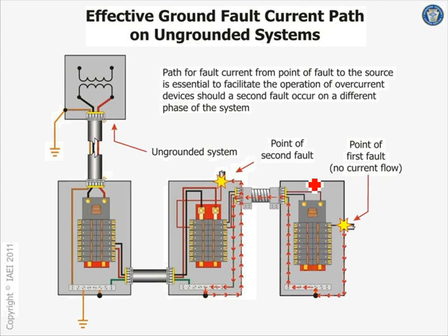You come over here. If you own and operate, you pull an equipment grounding conductor here. If you own and operate, then you come over here and create your own grounding electrode system right here. And then with your own grounding electrode system, you ground everything else. You do not need to pull that conductor in an ungrounded system, that conductor that ties this piece of equipment, unless you own and operate it.